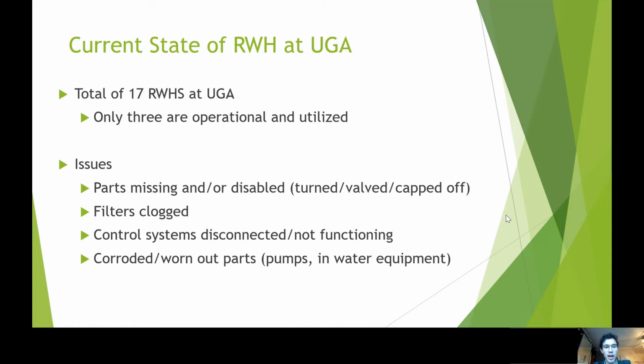Some of the issues with the systems that were not operational is that there were parts missing and/or disabled. Sometimes the water was just turned off to the skid or from the skid or to individual pieces of equipment. And this also included power. Filters were clogged. This included both pre and post filtration systems. There were also control systems disconnected or not functioning, which included building management systems not communicating well with other building management systems or relaying the information that they were supposed to. In addition, parts were simply corroded or worn out, and this related specifically to pumps and other in-water equipment.